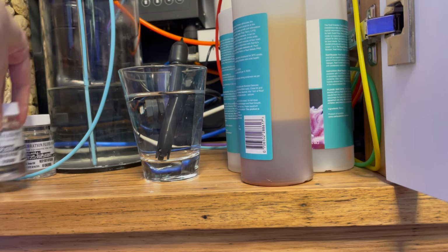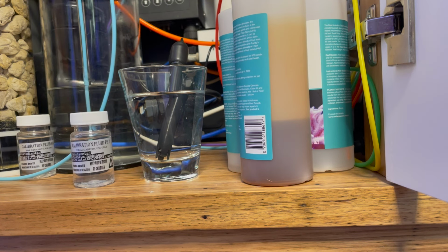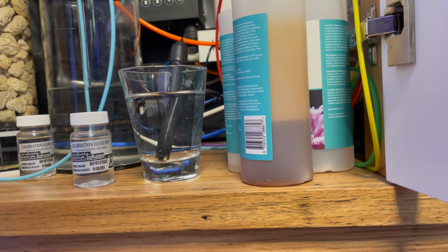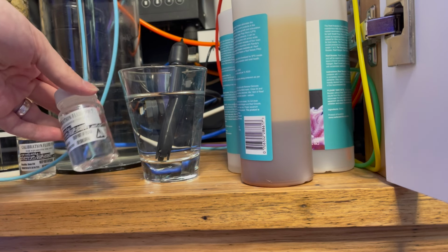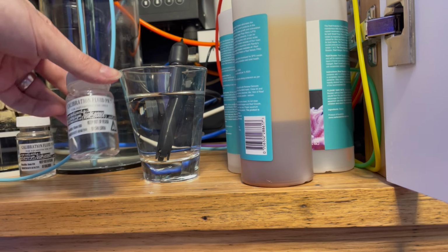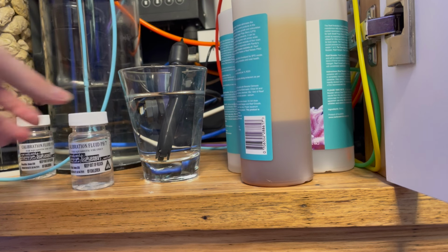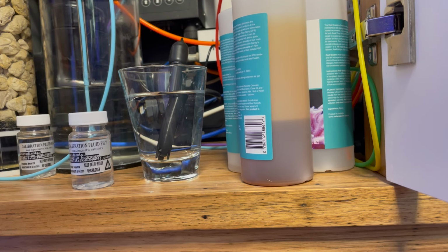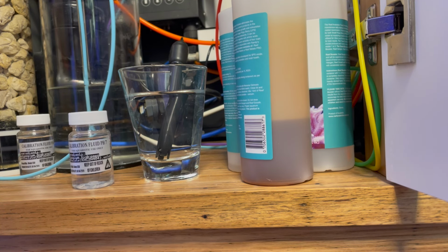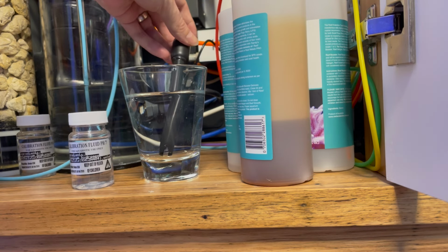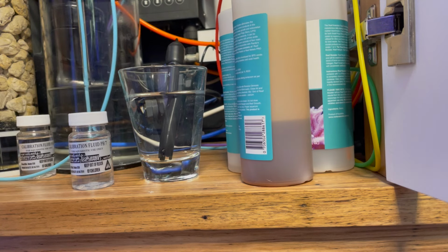The 3-minute timer is counting down over on the computer. And once that's finished, I'm sure you can guess what comes next, but we're going to repeat the process with a 5-minute timer sitting in the pH 7 and then press the calibration button. And once you've done the calibration against 4 and 7, calibration is complete, and we will put the probe back into the KHLab.